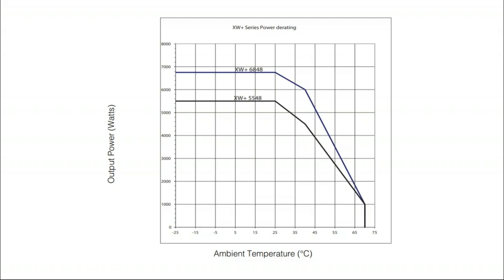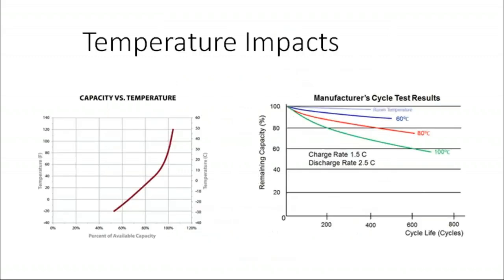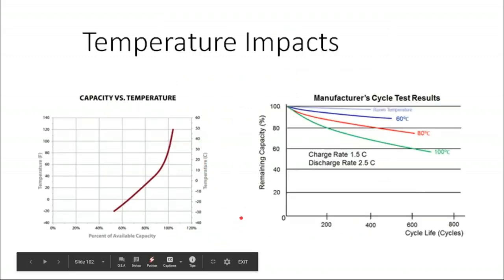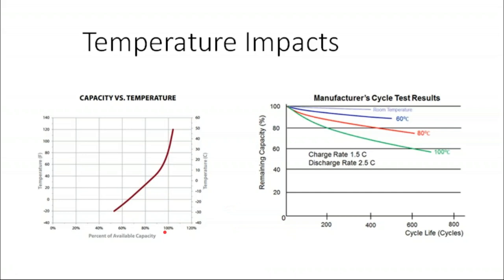Schneider's, for example, is a NEMA 1 inverter, so it has to go inside—it can't go outside. That can surprise a solar installer who is used to everything having tremendous environmental ratings. A common spot where I see batteries installed is inside garages, and that's not a terrible spot for them, although inside an air-conditioned space would be best, as temperature does impact batteries in a negative manner.